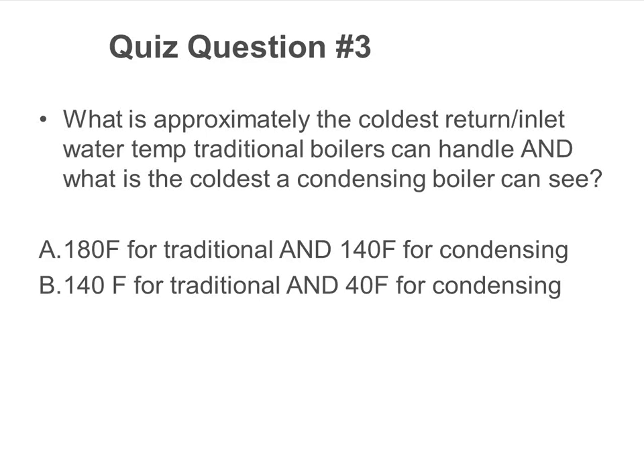Condensing boiler, the colder the water, the better. As long as it's not so cold we can't pump it anymore. So 40 degrees would be the right answer. B. 140 for traditional, 40 for condensing. Where you're going to see that 40 degrees is basically if you're using a condensing boiler to make domestic hot water and or snowmelt systems. So when you're designing a snowmelt system, you've got this condensate to get rid of.